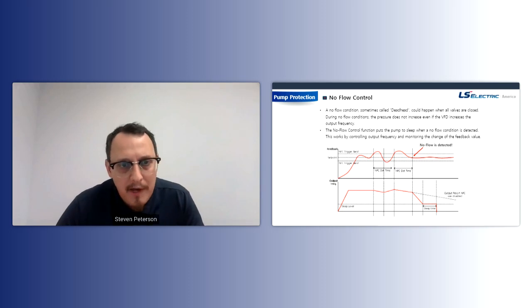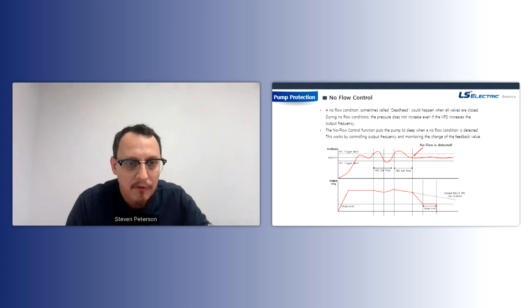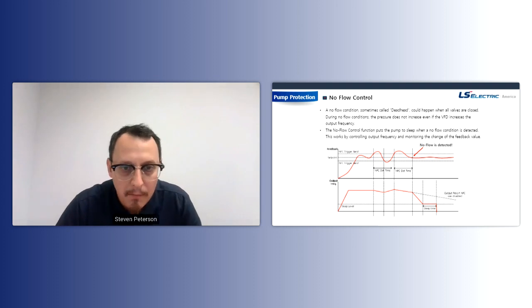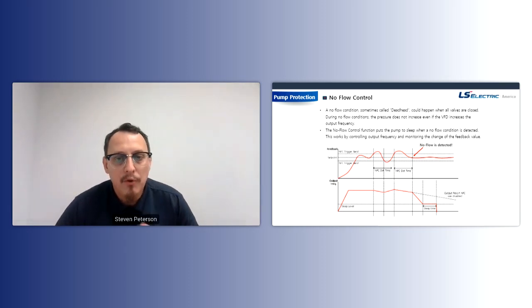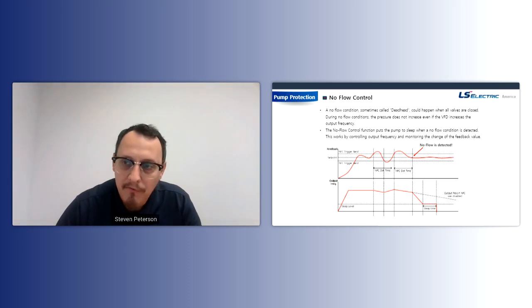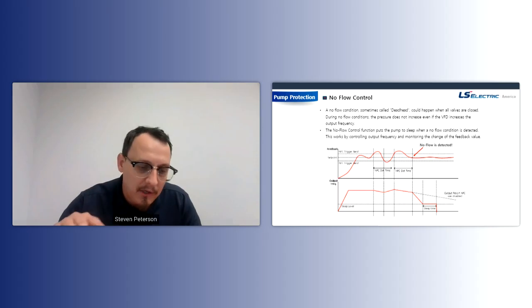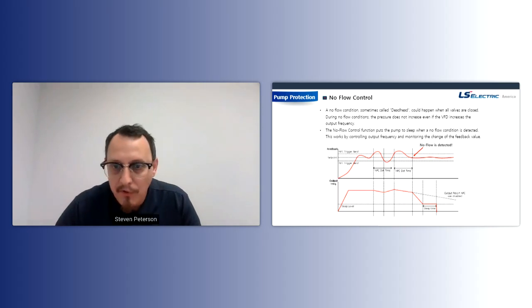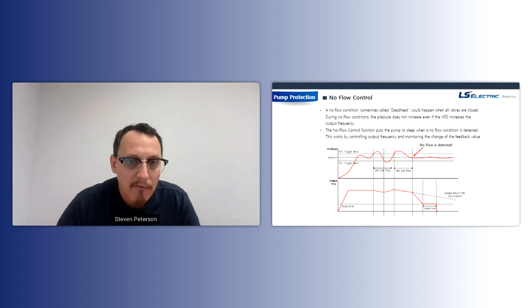So we add this no flow control function here. It's disabled from the factory, so you'd have to go ahead and enable it. And pretty much it's a percentage. So you're setting this no flow control trigger bandwidth. As soon as you enable that bandwidth, we're going to monitor whenever we're within a certain criteria of the set point in our feedback and our time. So we have a time related to that. We're actually going to actively adjust the output frequency and see what happens with the feedback. And then we can calculate if we're in a no flow condition.